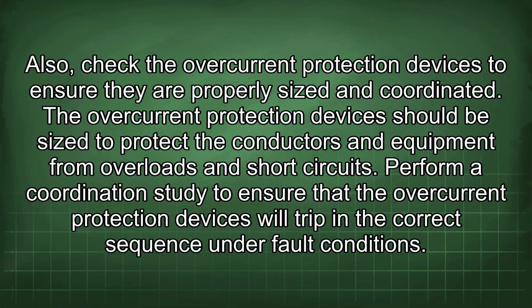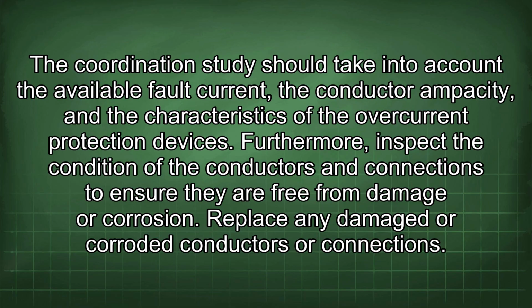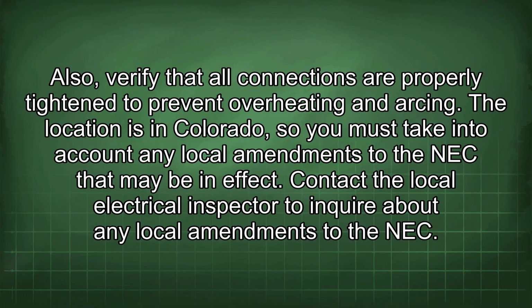Perform a coordination study to ensure that the overcurrent protection devices will trip in the correct sequence under fault conditions. The coordination study should take into account the available fault current, the conductor ampacity, and the characteristics of the overcurrent protection devices. Furthermore, inspect the condition of the conductors and connections to ensure they are free from damage or corrosion. Replace any damaged or corroded conductors or connections. Also, verify that all connections are properly tightened to prevent overheating and arcing.